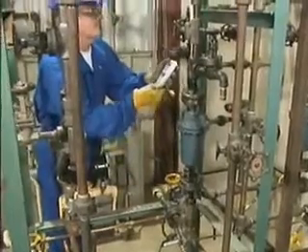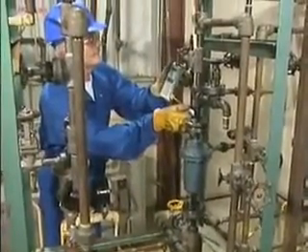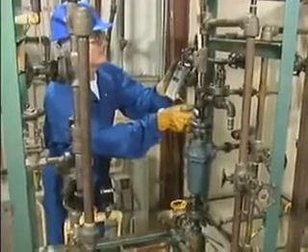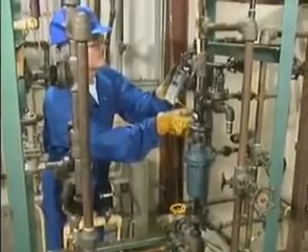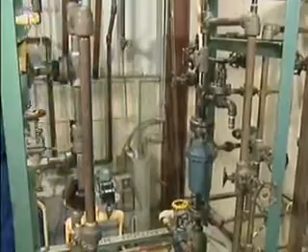But this doesn't mean that the trap outlet conditions are also normal. Outlet conditions must be checked separately. If the temperature at the trap outlet is also within the allowable range, trap conditions are probably normal for the temperature inspection part of the trap survey.